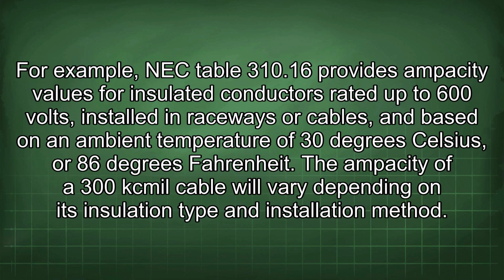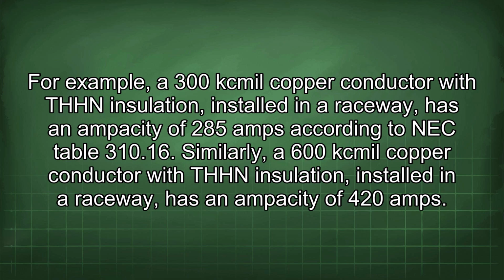For example, NEC Table 310.16 provides ampacity values for insulated conductors rated up to 600 volts, installed in raceways or cables, and based on an ambient temperature of 30 degrees Celsius or 86 degrees Fahrenheit. The ampacity of a 300kcmil cable will vary depending on its insulation type and installation method. For example, a 300kcmil copper conductor with THHN insulation installed in a raceway has an ampacity of 285 amps according to NEC Table 310.16. Similarly, a 600kcmil copper conductor with THHN insulation installed in a raceway has an ampacity of 420 amps.